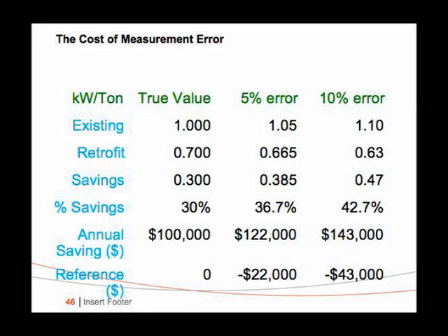In doing all of this, there's a philosophy thing which I think the market still does not accept. It is assumed that if you don't have accurate instruments, you can achieve all these numbers, like 0.6, like 0.48. And my experience is you cannot. That's why in the world, there are hardly any credible claims of high efficiency, because the measurement equipment is not good enough.